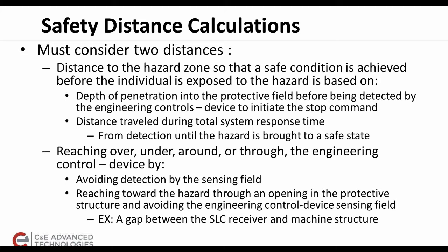Then there's also the reaching over, around, or through of the control device, such as reaching around between the safety light curtain and a protective structure. The location of the protection device then needs to be mounted at the furthest distance.